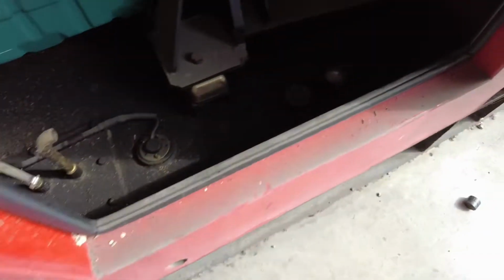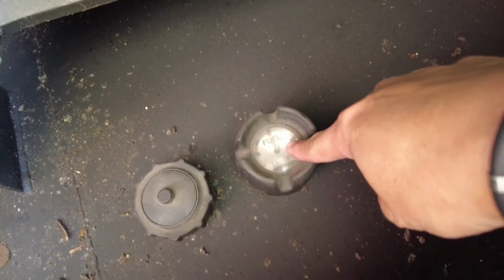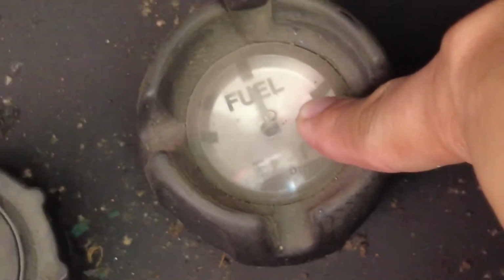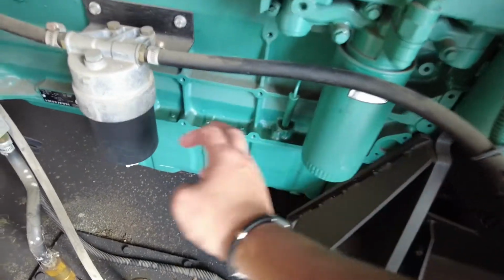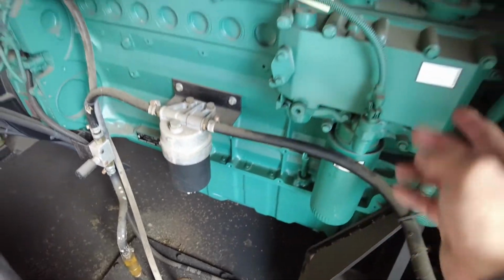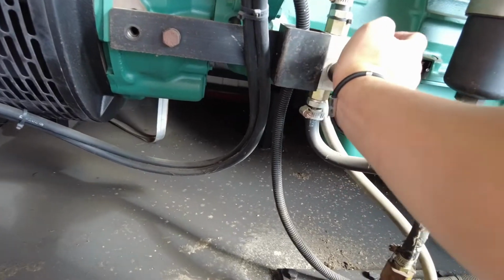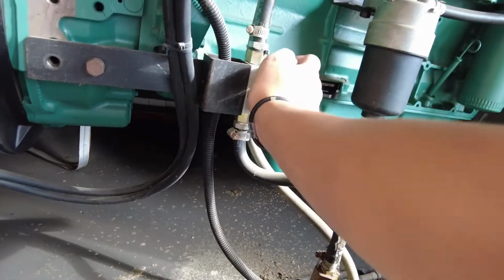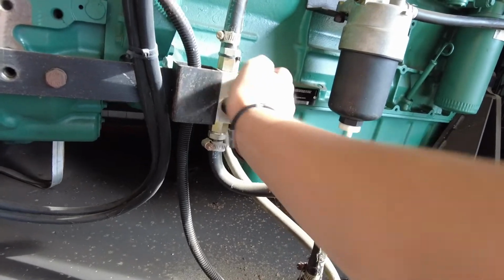Let's check the fuel level. Fuel level is about 50%. This is a fuel filter, oil filter, engine oil filter, no leakage. Okay, let's pump. Allow some airlock inside to come out. Okay, after pump, no problem. No loose wiring. Check the belting. Belting no broken. All belting okay. Fan no obstruction.